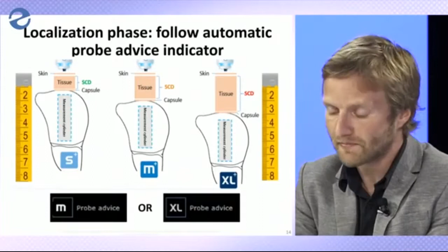If you want to check your quality of signal before pressing the button, I would like to insist that what Echosens recommends is really to take care of the ultrasound signal that you get on the screen. As you can see on the image here, it's really important to get nice uniform layers, which is a typical signal of the liver within the measurement area, the region of interest.